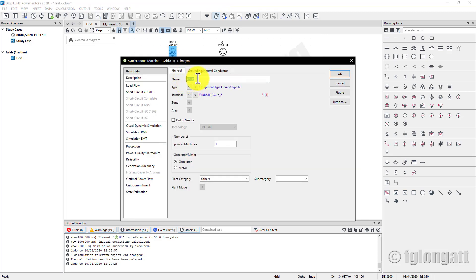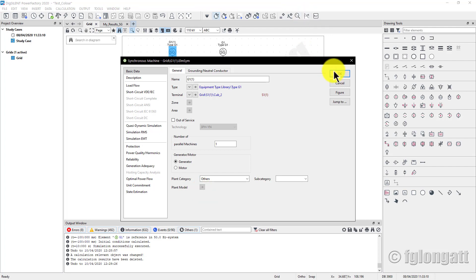The generator element has its type and is ready for load flow. But if you are planning to run a dynamic time-domain simulation to get, for instance, frequency response, the controllers are simply not there. For that reason I don't suggest copy-paste, especially if you are working with a wind turbine model that took a year to create with thousands of DSL and composite models. Doing copy and paste loses the connectivity between controllers, measurements, and network components.